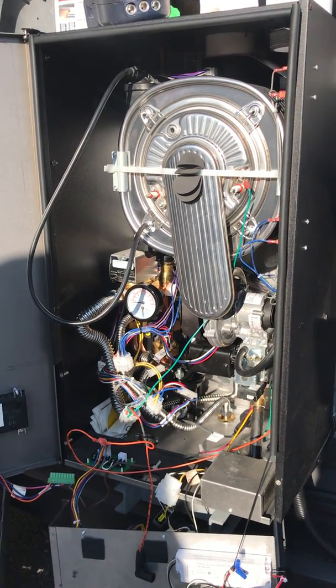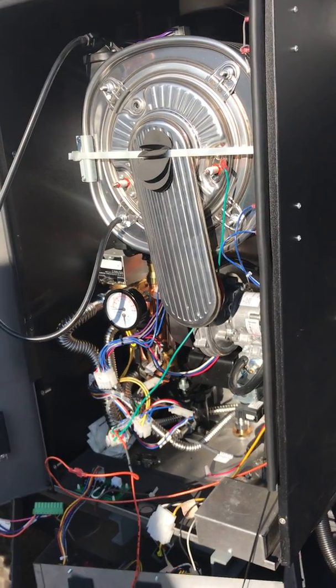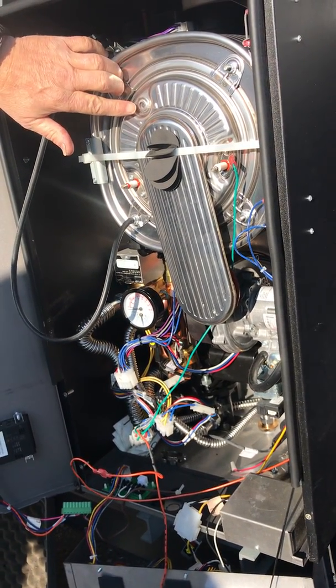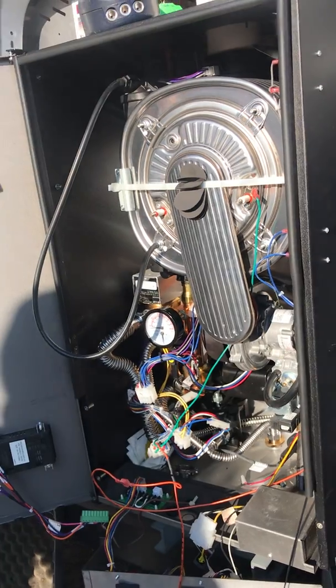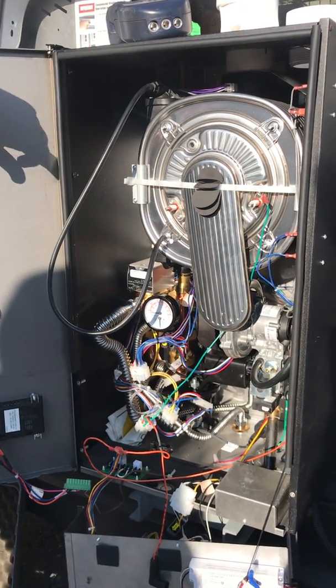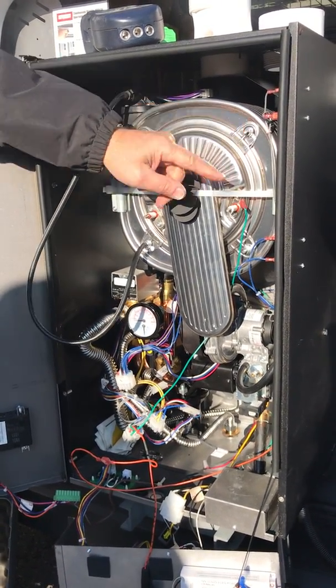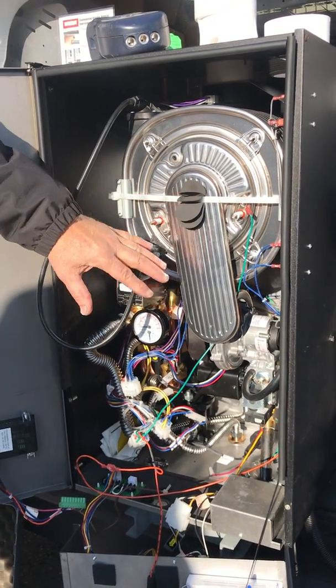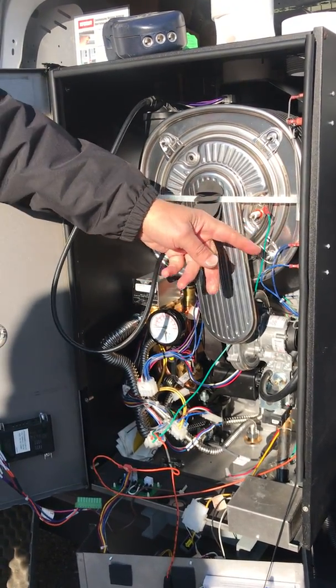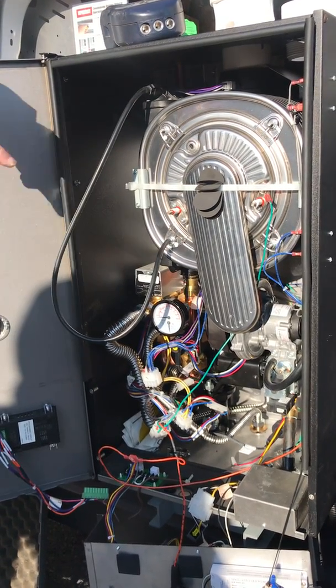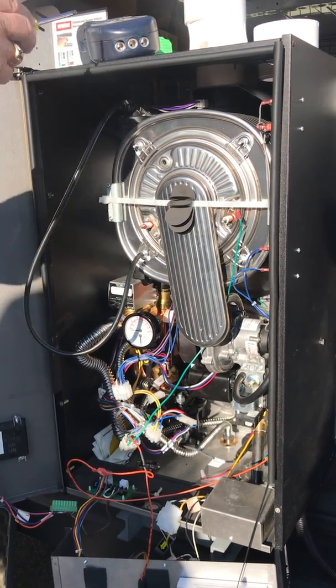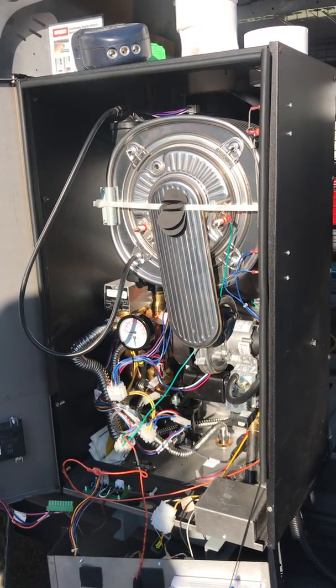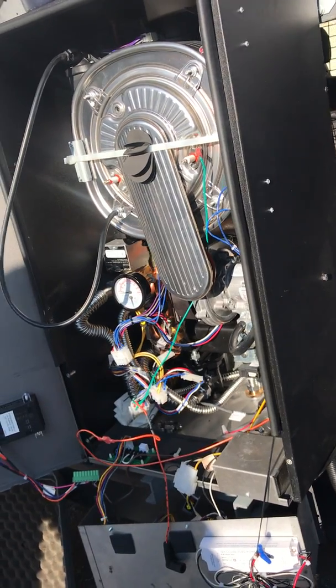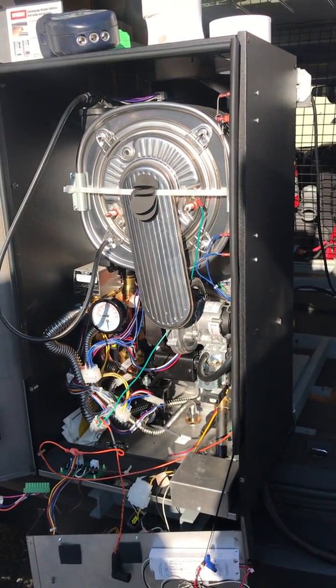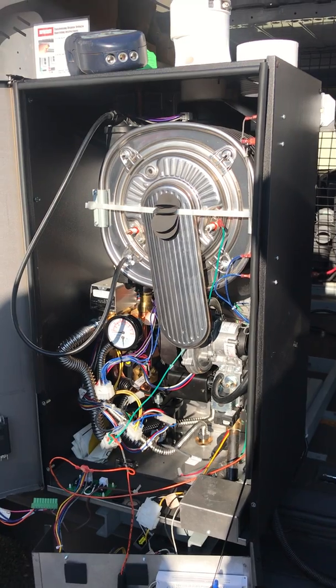Now, on a regular maintenance, what do you recommend doing? Regular maintenance, I would take a look at that and see what it is. I would do my combustion test and see where I am on my combustion. And if I needed to clean it, I'm going to pull these 4 off, pull my wires off, and my ground wire. I'm going to pull this out, and I'm going to spray CLR on the inside and use a nylon or a brass brush and just clean the inside, flush it out with some water, and stick it back in. Okay. And do my combustion test and just check and make sure.